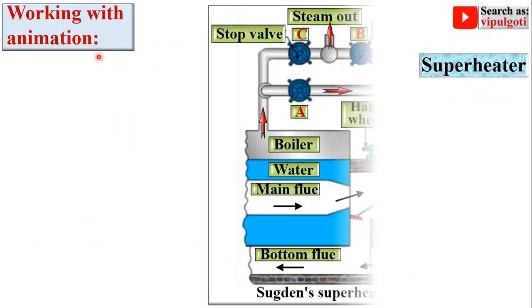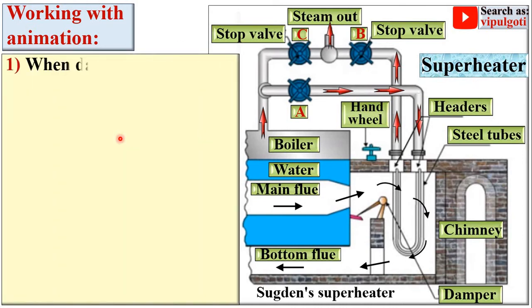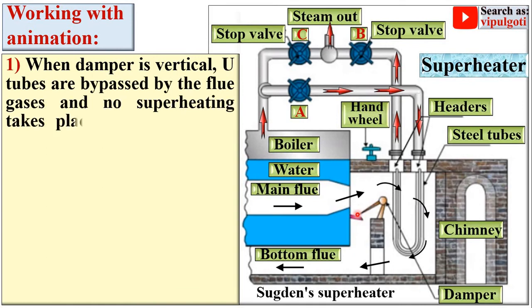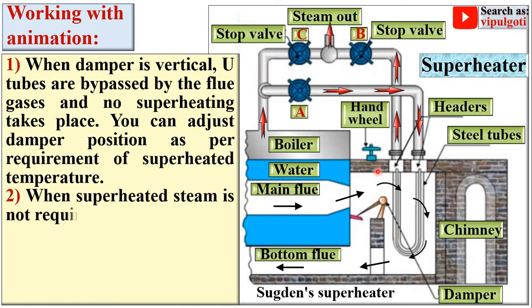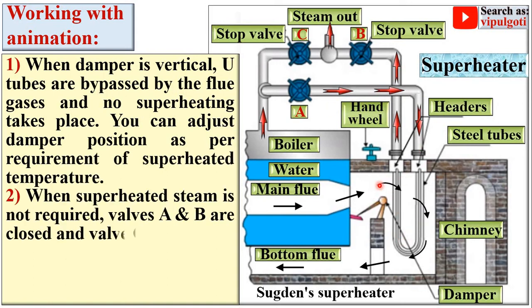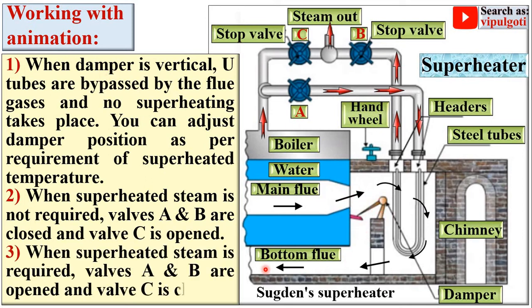Now, the working with animation of the superheater. When the damper is in the vertical position, the U-tubes are bypassed by the flue gases, and so the flue gases flow around the tubes and no superheating takes place. You can adjust the damper position as per the requirement of the superheated temperature of the steam.